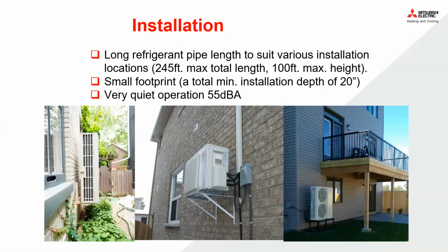And then when you look at installation, the condensers can be placed almost anywhere. They just need to be above snow level, but as you see, they can be mounted to a wall, they can be mounted off the ground, you can put them on roofs. In a lot of countries, that's where they're put. And then with refrigerant line, you have pretty good lengths depending on the capacity, maximum 245 feet, but you can run these lines pretty much anywhere you need to.